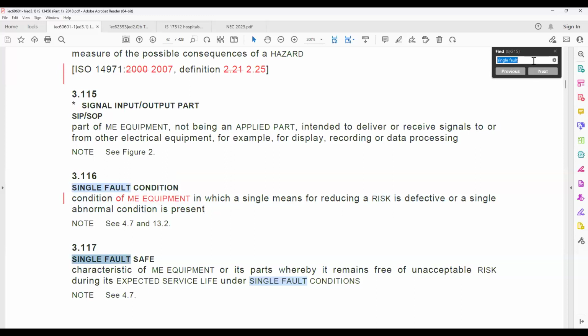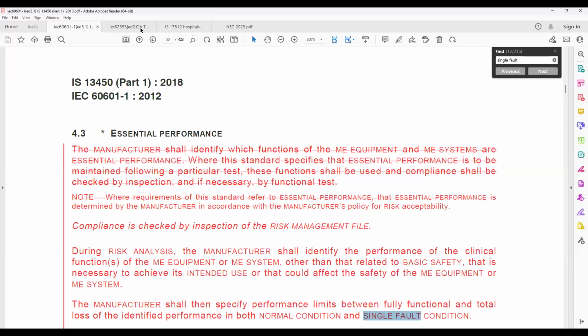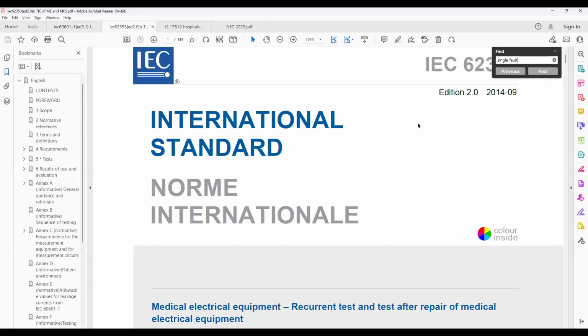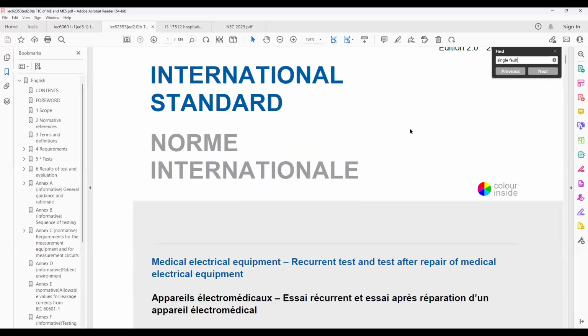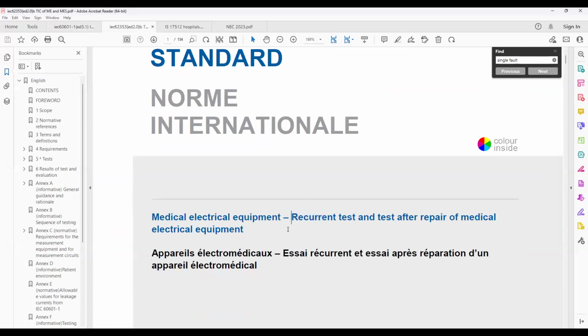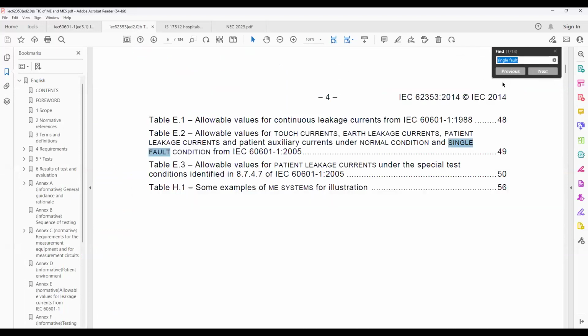And it is not a simple subject to handle. Say, for example, in this particular standard, single fault is explained in 215 places. Similarly, the next standard, IEC 62353, the medical electrical equipment, recurrent test and test after repair of electrical equipment. What do you do? How do you do the repair, and what are the considerations? Here, for example, the single fault condition is explained 14 times. So basically, handling the single fault condition is decided by the power supply. And if you don't handle the power supply properly, then actually you are in trouble.